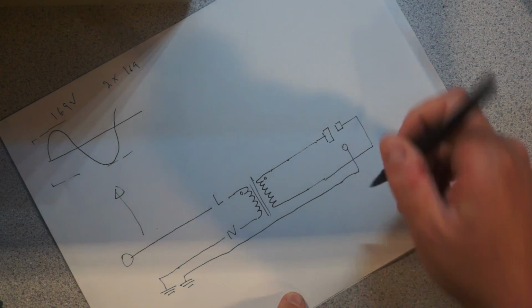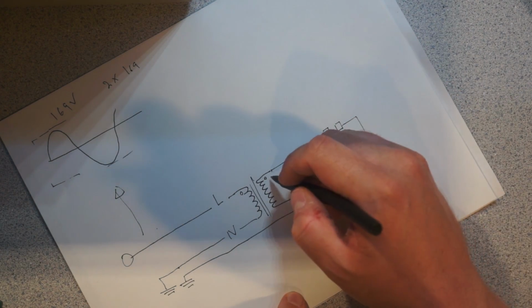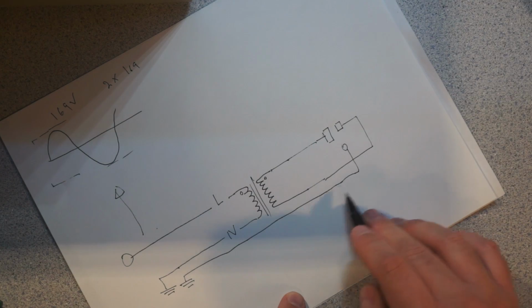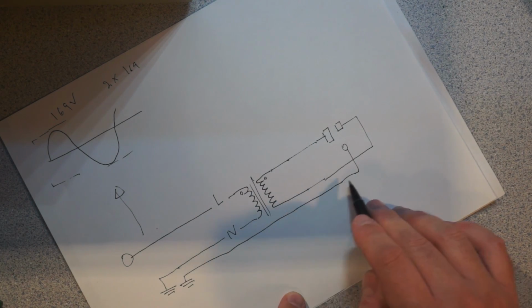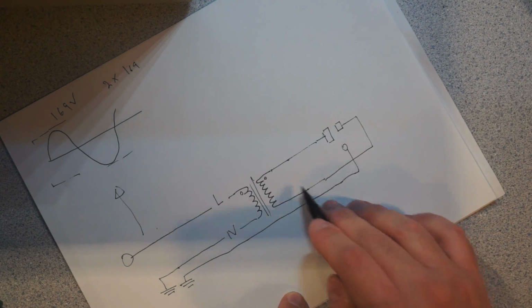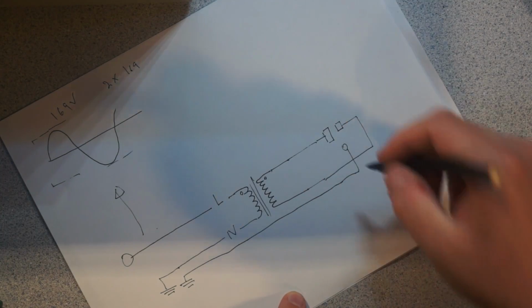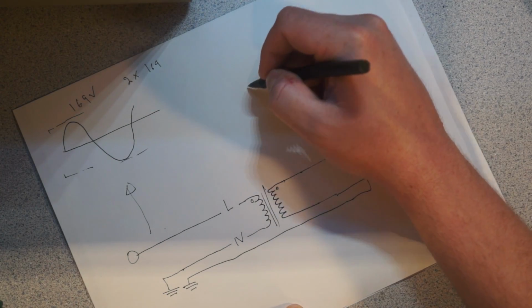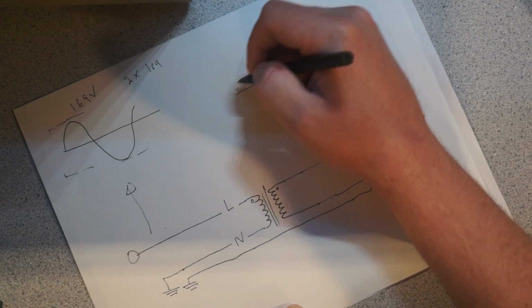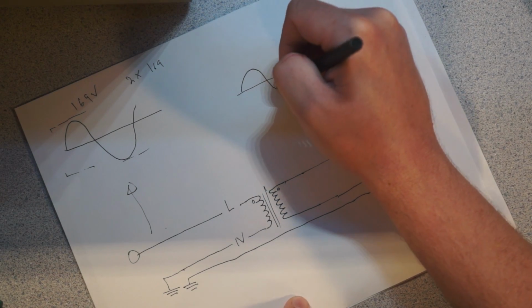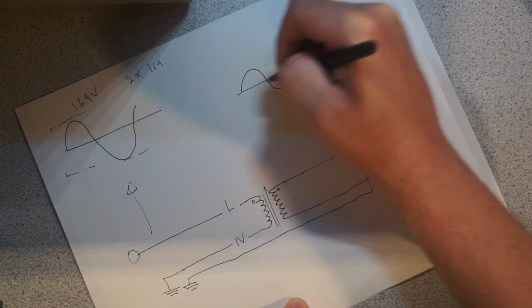So what happens is that because there's a small amount of leakage here, and most of it's probably leaking to ground, because again you've got ground in close proximity - they're inside the transformer, bundled together - what you instead wind up with is 2 waveforms that are 180 degrees out of phase.